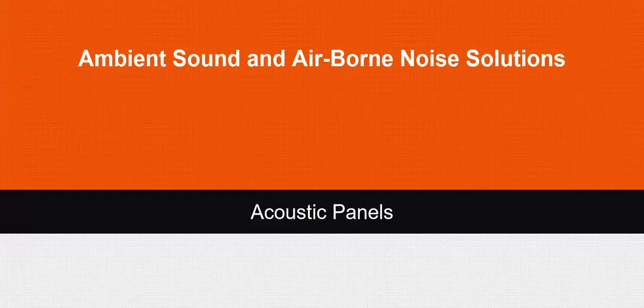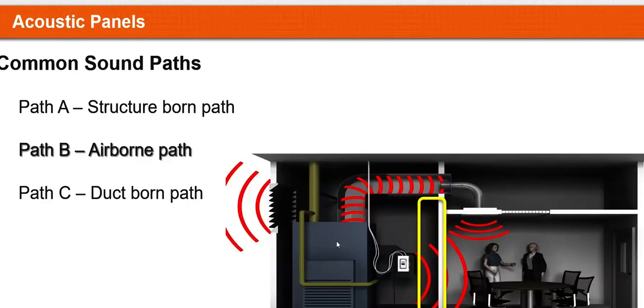So moving on to acoustical panels now, we're going to start talking about the different sound paths from structure-borne, which you treat with your typical different types of isolators from neoprene pads to true spring isolators. In this specific session, we're mostly going to focus on airborne path or ductborne path. Specifically, a reminder, and this is a good infographic here that shows you if I were to add a silencer on the discharge here on the duct coming from the top, that is going to block some of the airflow. The silencer inside is meant to impede some of the lower frequency waves from passing through, and the waves that pass through get absorbed by means of friction and changing your sound energy into heat and kinetic energy through vibrations. But by obstructing the airflow, you're going to create back pressure to the fan.